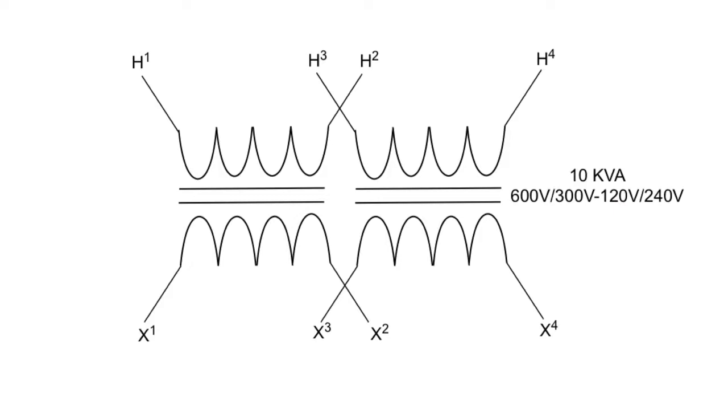Now, what we're going to do is determine each winding rating. Let's talk about the high side first. We look at the lower voltage, 300 volts. With these two voltages, 600 and 300, we're going to take the 300 volts, and that is our winding rating. Let's get that written in there.